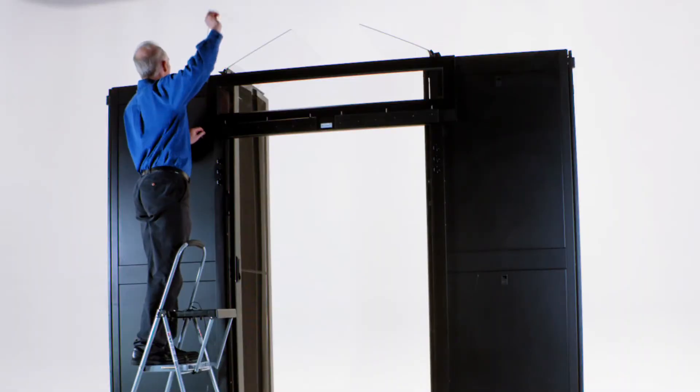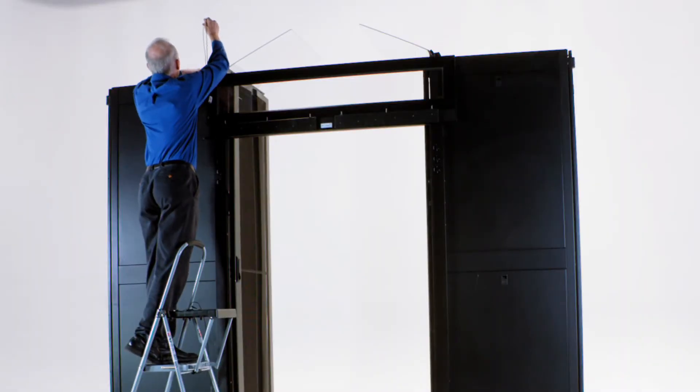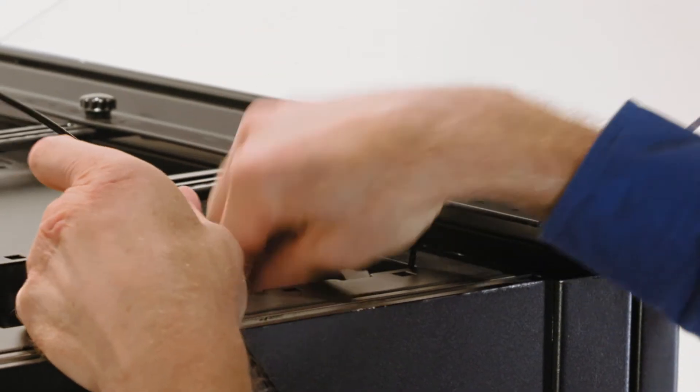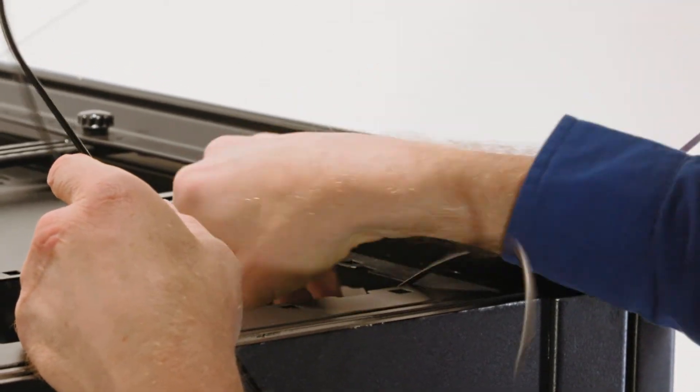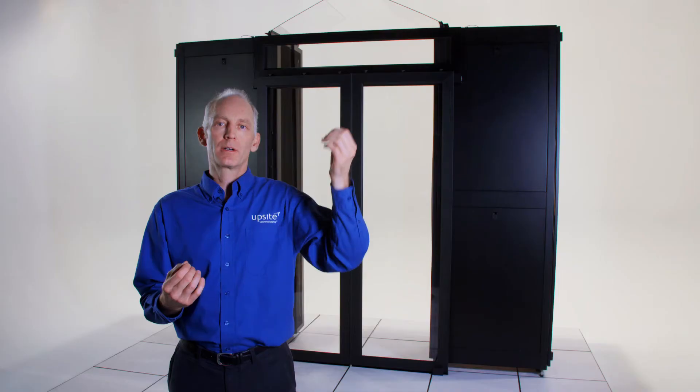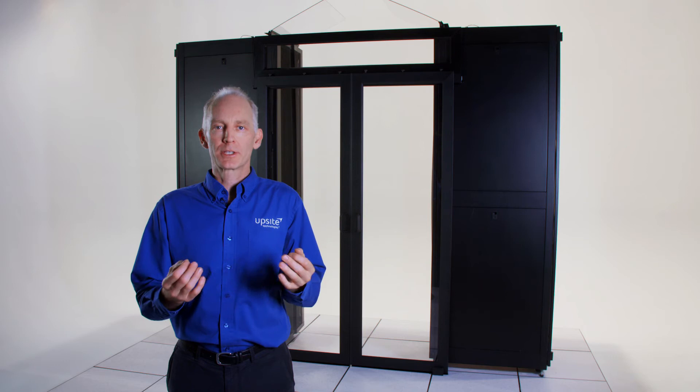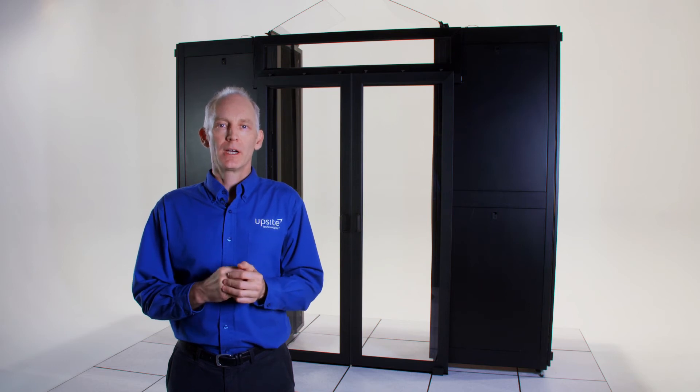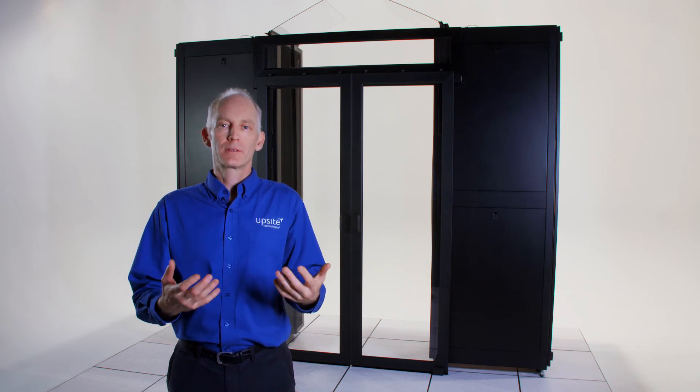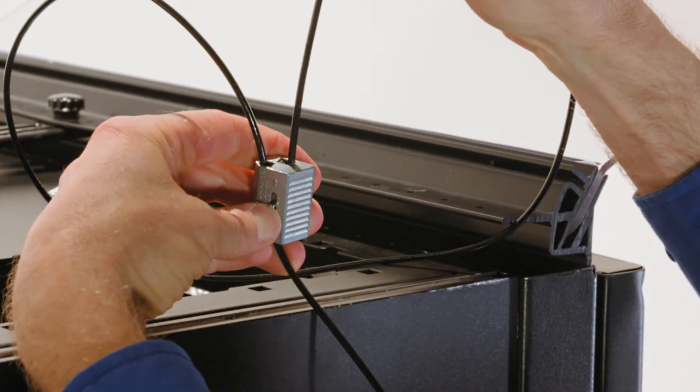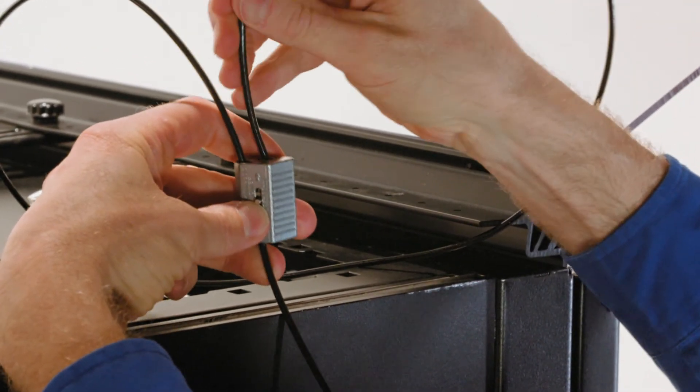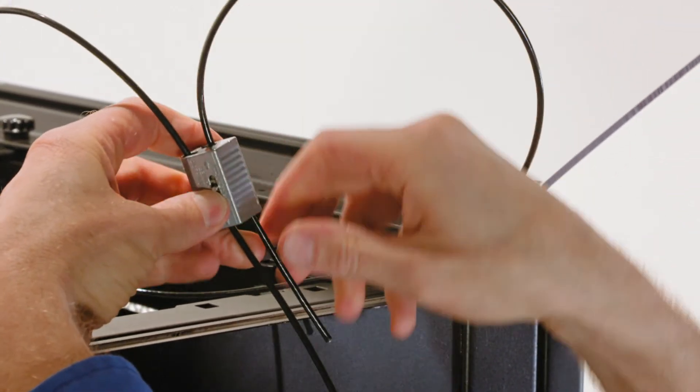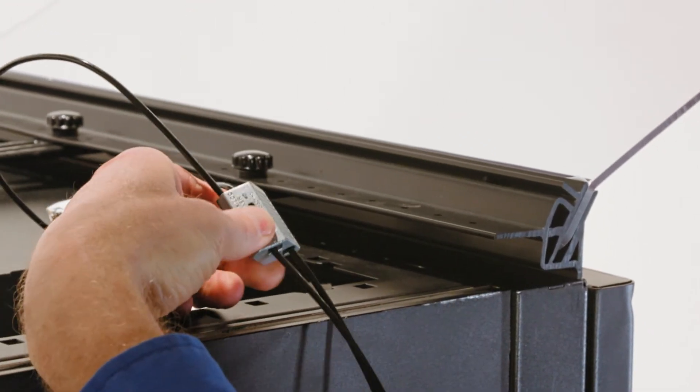Now you're ready to run the tether up over the top of the cabinet, either through an opening in the top of the cabinet or some other secure overhead structure such as cable trays. Something overhead that could hold the weight of the doors. The tether is there so that if the doors ever are knocked off they won't come off completely. They'll stay in place.